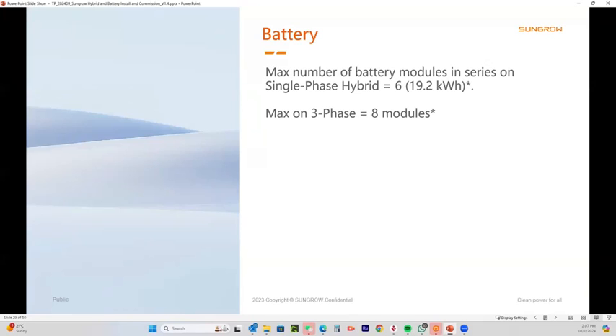Now, the maximum number of modules in a series on a battery stack for the single-phase hybrids is 6, and I'll explain why in a moment. That's 19.2 kilowatt hours. And if you are using a three-phase inverter and the SBR batteries, the maximum is 8 modules.